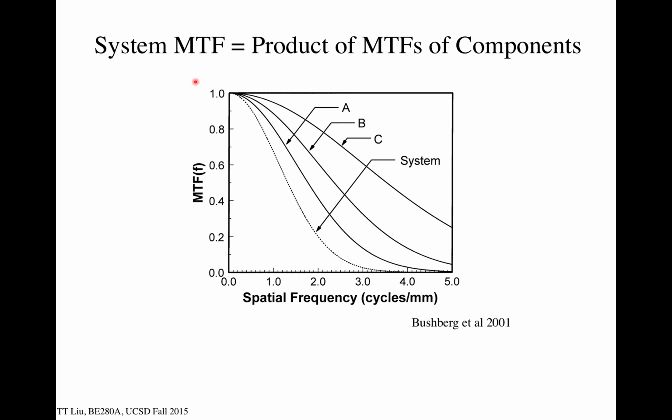And then we characterize the system. This goes all the way back to what we talked about in the first lecture. These systems can be quantified in terms of their ability to resolve small things, or what is their resolution, by the modulation transfer function. And the modulation transfer function is plotted in the Fourier domain, right? It's spatial frequencies, cycles per millimeter.